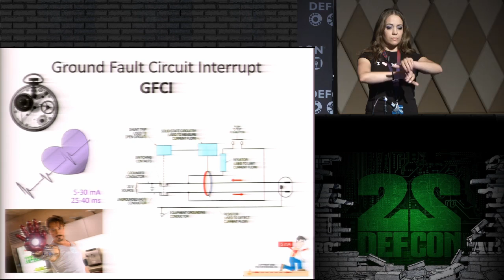According to the right-hand rule, if the currents are going opposite directions and they're the same magnitude, they should cancel each other out, so there should not be a current in that wire. If it detects a small current there, calibrated to I think 3 or 5 milliamps, the solid-state circuitry will inform the shunt trip to open the circuit, and it'll save you from electrocution.